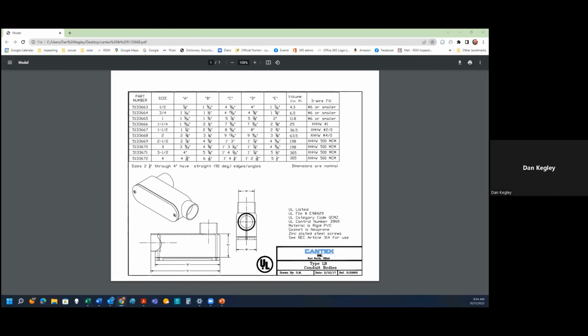All right, one more question here on the chat. So he's asking for a clarification. So an LB or a conduit body can be used as a splice point to connect an alarm float wire to the low voltage wire in a holding tank installation. Is that correct? Correct. You could use an LB as a splice point for putting wire nuts to put the low voltage together. Yep. It's just when we do the pumps that it's something different. Correct. Yep. So the housing's not allowed to have that receptacle. You know, there's not enough room to put like a receptacle in there with a little box and receptacle to plug in that pump. Gotcha.